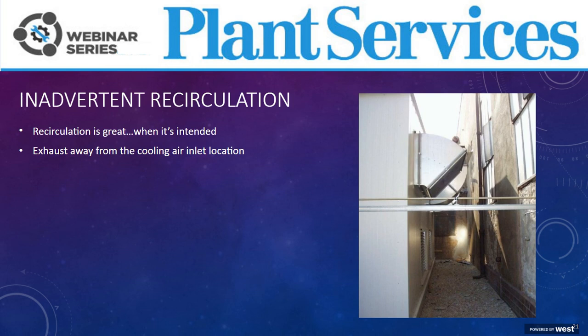The best way to avoid inadvertent recirculation is to ensure that it works properly. But there are going to be times when compressed air equipment is accidentally recirculated into your cooling air. This typically is when the cooling airflow pattern is poorly thought out, or when systems evolve over time and equipment is added bit by bit over the course of many years.